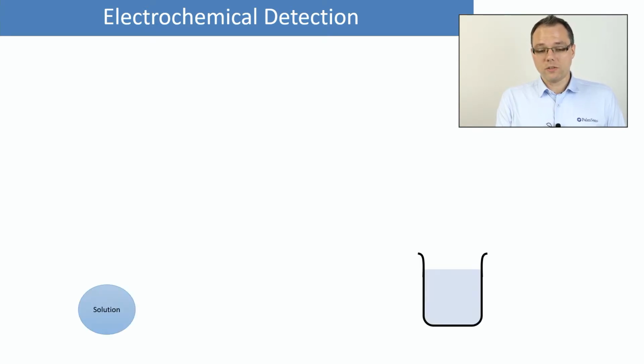well, now we have learned the theory behind it, and we see, okay, it's not awfully complicated, it's all right. But then this measurement, isn't that complicated? Because it sounds like you need a lot of things, like you need 2 electrodes. Well, it's not that complicated. You need your sample, of course, and if you have a good compact system, you just need to have this one chip or one probe where you have your reference and your ion selective electrode integrated.